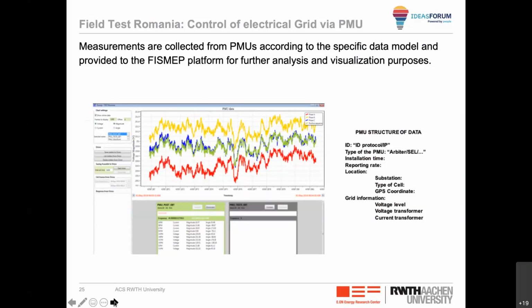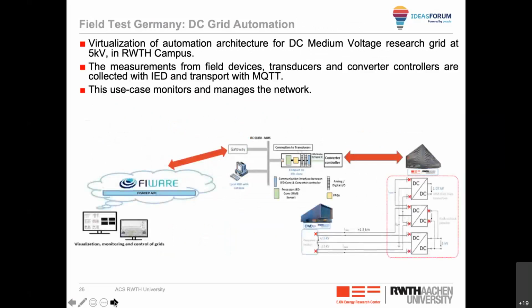The field test, which has been developed in Germany, considers the automation of the DC grid. In the field test, the visualization of data in the DC medium voltage has been taken into account. Accordingly, we gather data from the intelligent electrical devices, so-called IEDs, and send the data to the platform via MQTT.